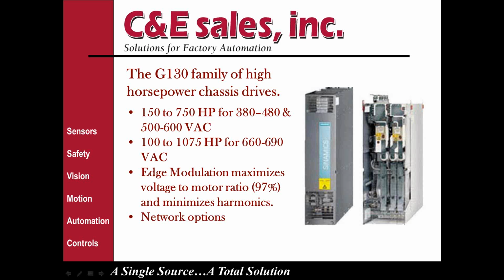It's for higher horsepower applications. And these are chassis drives so that you would mount these in your enclosure. They're available in 150 to 750 horsepower in the 380 to 480 volt range and the 500 to 600 volt range. They're up to 1,075 horsepower in the higher voltage, 660 to 690 range.